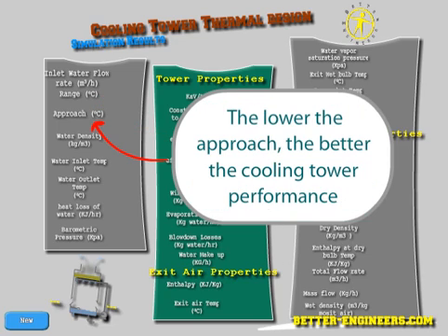Approach: the approach is the difference in temperature of the outlet cold water and the ambient air wet bulb temperature. The lower the approach, the better the cooling tower performance.